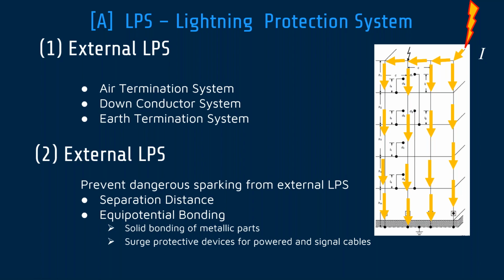Now understand, when we start talking about surge protection, this is another part that needs to be cleared up across our country: surge protection in the context of an internal LPS is not the surge protection to protect electronic equipment or electrical equipment in the building. The surge protection applied here is as a part of the equipotential bonding. So there's two strategies that we need to apply when we talk about this dangerous sparking that's been created by the external LPS.